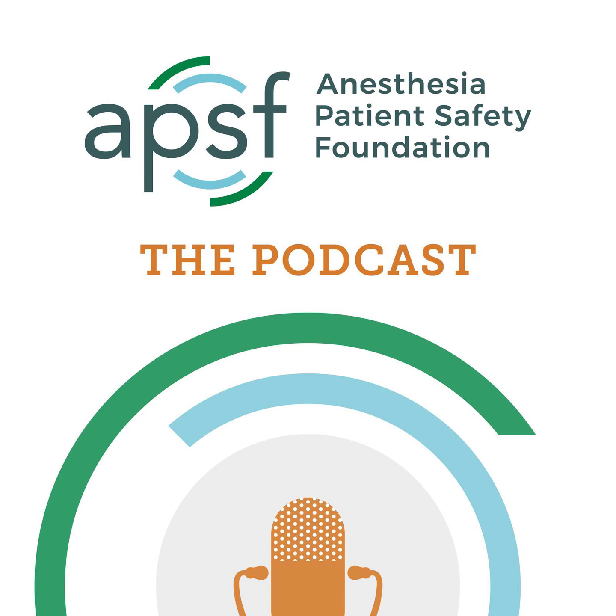Another important area that we need to discuss related to the low pressure alarm are false negative situations. This may occur when there is a real low pressure condition in the breathing circuit, but the low pressure monitor fails to alarm. This may be a cause for alarm, so let's talk about why this might happen. It may fail to alarm because the threshold criteria for the minimum pressure was reached at the location in the breathing circuit of the pressure monitor. Thus, the most common false negative situation is when the anesthesia professional does not set an appropriate minimum pressure threshold. If the minimum pressure threshold is set too low, then the monitor may fail to detect a partial disconnect.